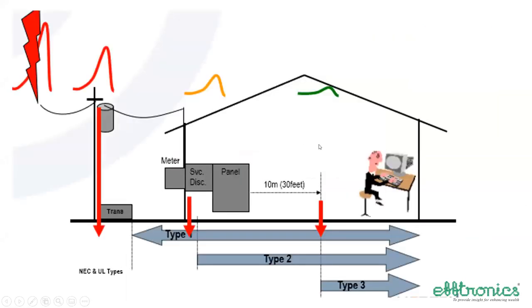How are the protection arrangements done in general? Let us consider that there is a computer in a home and it gets a power supply from the outside service provider. How it happens: a lightning has occurred, and we know that all the outdoor wires are open wires. So they induce a very high voltage, and then that comes to the transformer. At the transformer, it gets reduced because of the high to low conversion. And then it enters into the house.